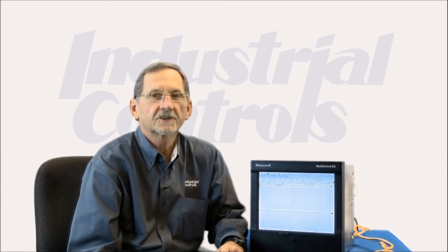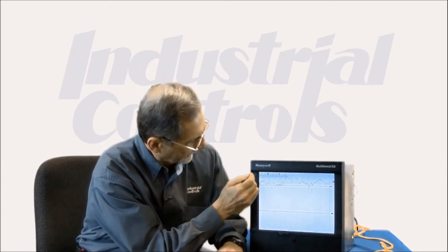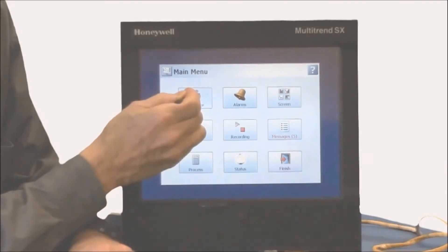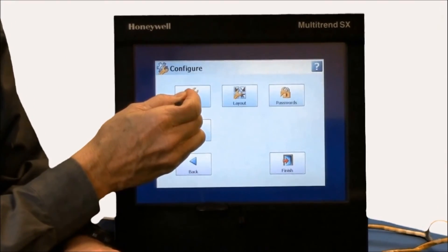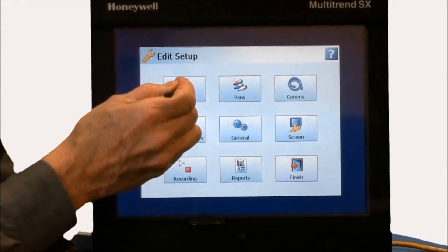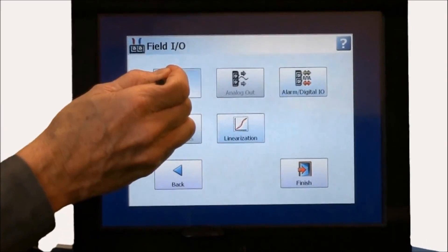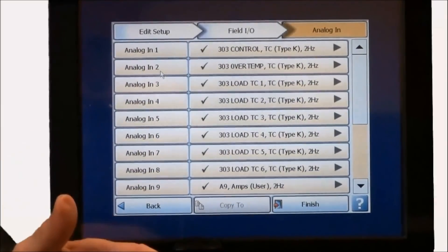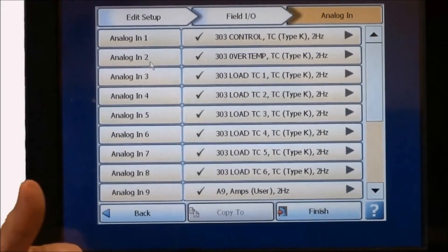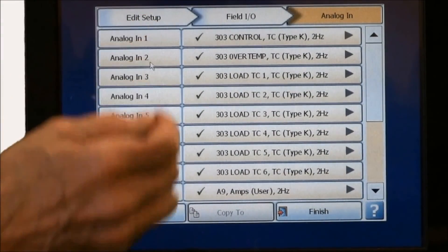Let's take a look at how easy it is to configure a paperless recorder. By touching the menu icon, then configure, setup, edit, and analog inputs, this is where you identify what the input types are — thermocouple, RTD, 4 to 20 mA — it's all universal inputs.